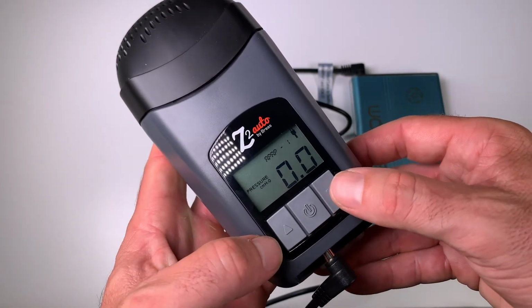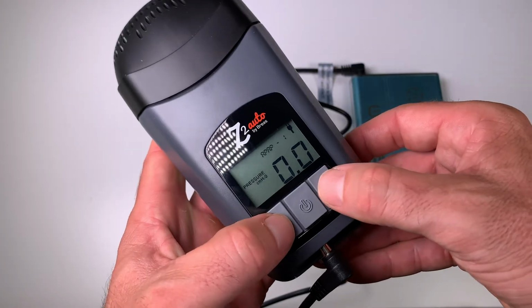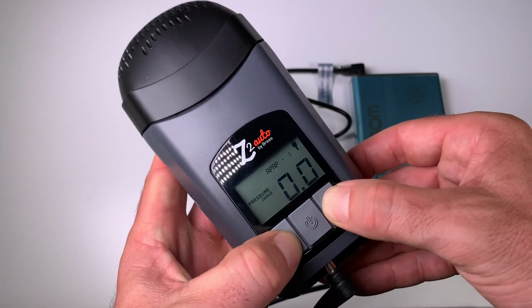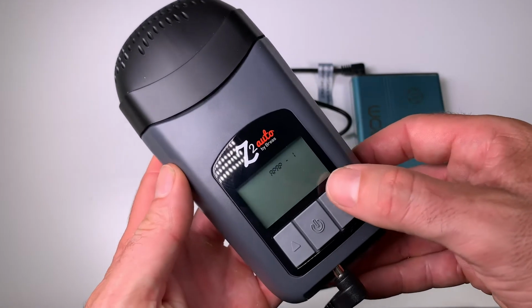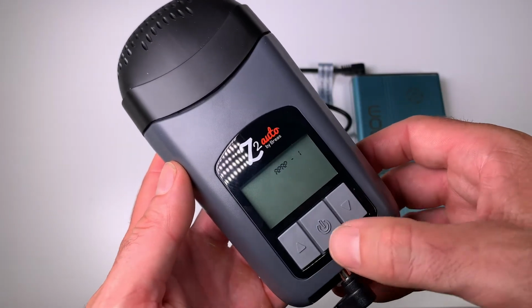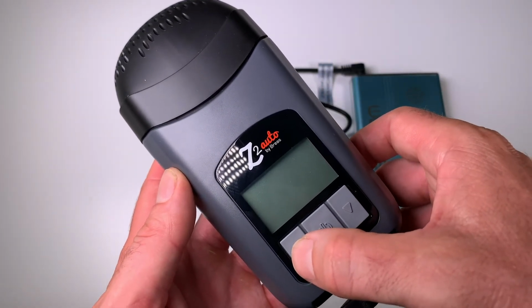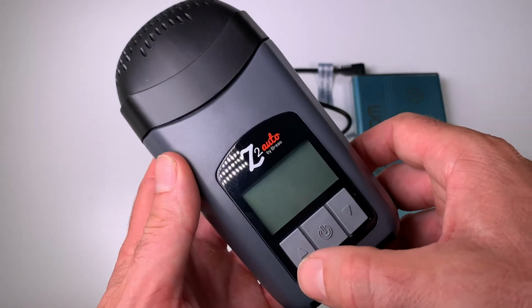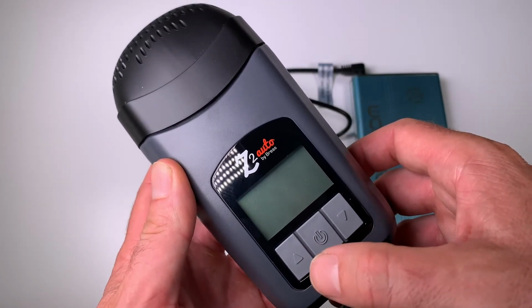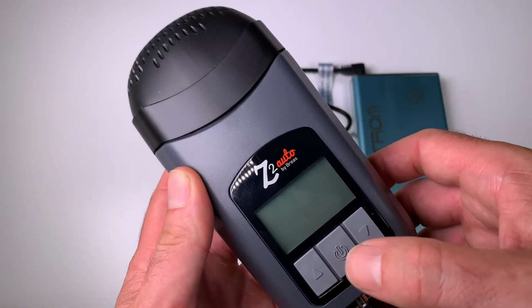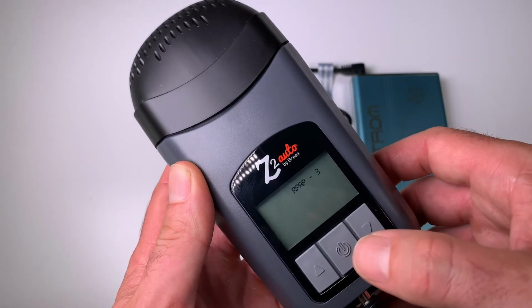To open them up, we just press the up and down arrows simultaneously, hold them down for about 2-3 seconds, and it'll start flashing at the top here, APAP 1. It goes APAP 1, APAP 2, APAP 3, and the higher the number, the more pressure relief you're going to get.